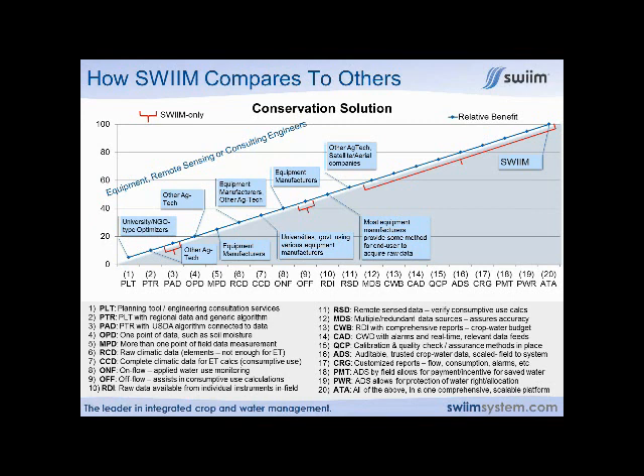We use some of them. We use some of the ones that have been around for a long time that our team is comfortable with their calibration and accuracy, but we don't use a lot of them. We have a handful of them that we're comfortable with. Sometimes we have to go out to the field and actually retrofit units if we know that they're calibrated and solid. But all of those folks are down here, getting—look down here on my little chart—one point of measurement, more than one point, a couple points of measurement.